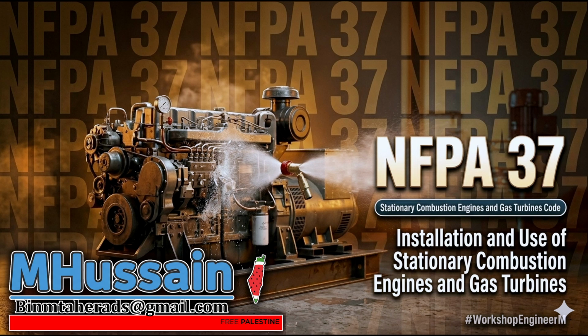25 feet, that's huge. Why so far? 2 reasons. First is radiant heat. If the generator is engulfed in flames, a window 10 feet away will just shatter from thermal shock. And then the fire just walks right into the building. Exactly. The second reason is carbon monoxide. Oh, right, the exhaust. Yeah, if you park a diesel engine 5 feet below a hospital's fresh air intake, you are pumping lethal exhaust directly into the patient wards during a power outage.